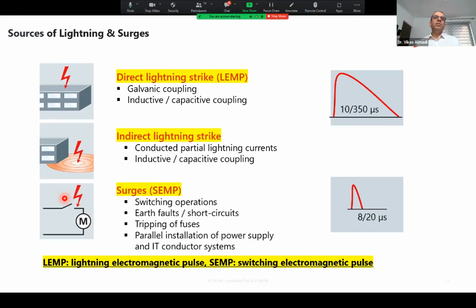So when we talk about indirect lightning, that lightning has taken place somewhere else, but the effect of this lightning is seen in our premises as an inductive effect or a capacitive effect, in the form of some surges which are appearing on the line. And surges themselves are due to the switching operations, heavy loads, inductive loads, capacitive loads. When they switch on or off, it may be in your premises or out of your premises, connected to something nearby.